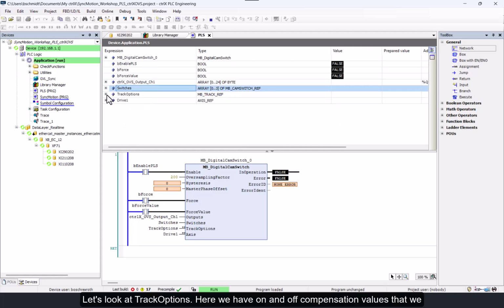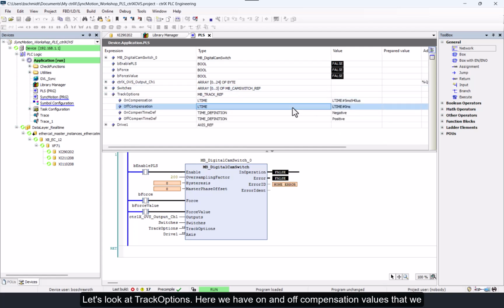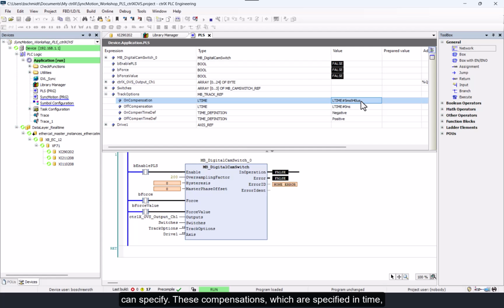Let's look at track options. Here we have on and off compensation values that we can specify. These compensations, which are specified in time, are used to compensate for electrical, mechanical, or processing delays in the system. Let's say I'm using this PLS output to trigger a high-speed camera system that takes a snapshot of the printed image on a printing machine. If I observe that the printed image is shifting in one direction as the machine speed is increased, I would adjust the on compensation until the image stays fixed in the camera view over the entire speed range.